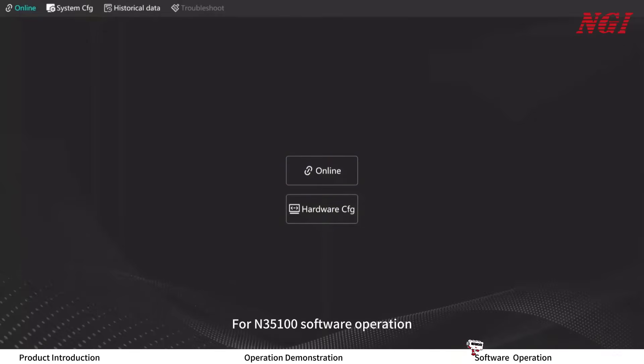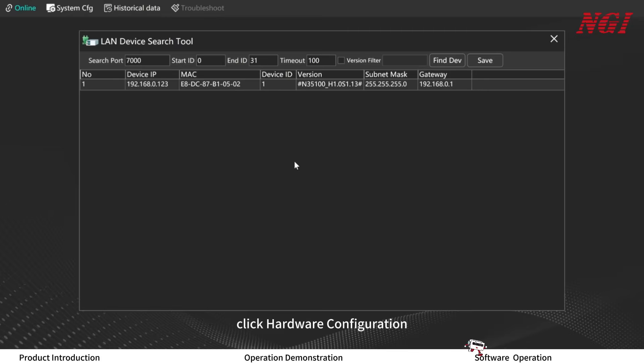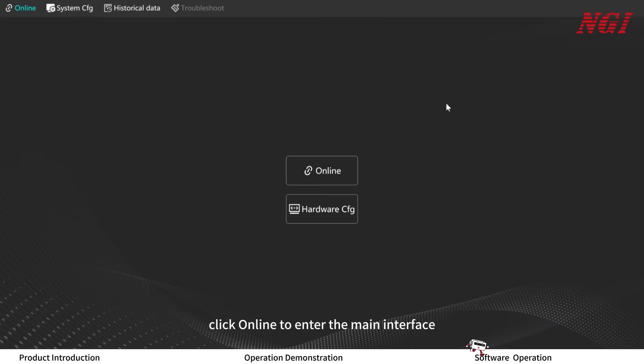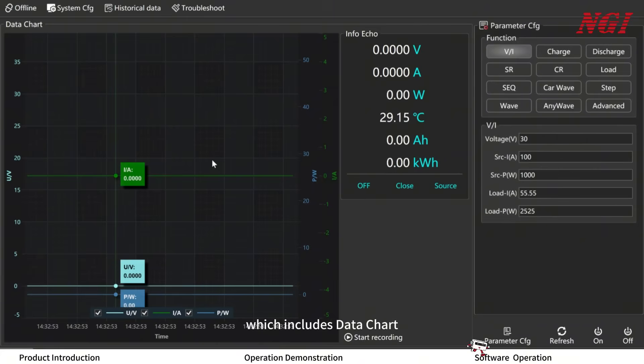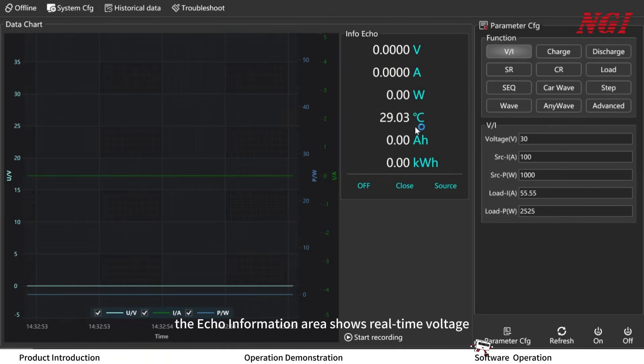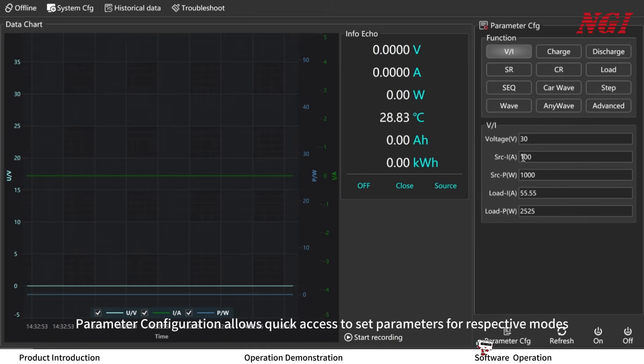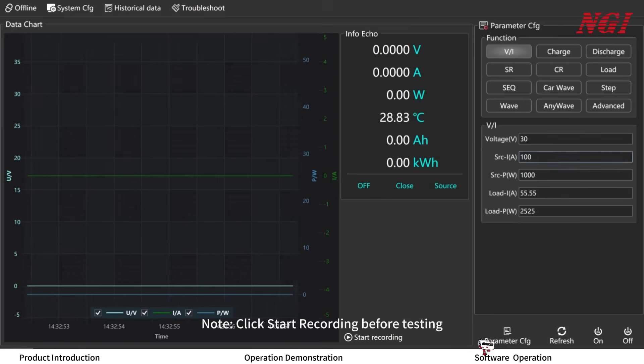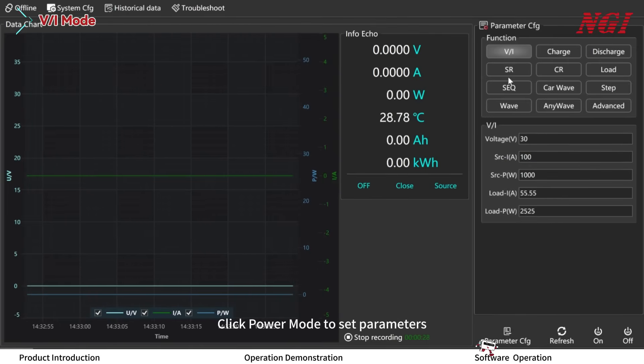For N35100 software operation: click hardware configuration, then find devices, select and save the configured subnet, and click online to enter the main interface. The main interface includes data chart, echo information, parameter configuration, and start recording. The data chart displays real-time voltage, current, and power. The echo information area shows real-time voltage, current, power, temperature, ampere-hour, watt-hour, and power supply status. Parameter configuration allows quick access to set parameters for respective modes. Click power mode to set parameters.